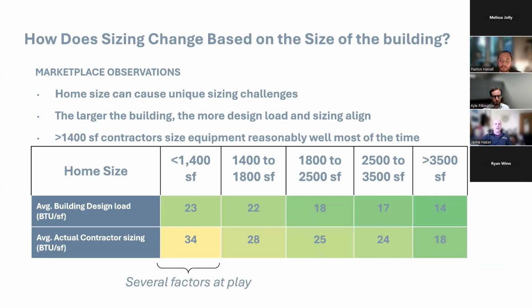As the house gets bigger, the design load of the heat pump and the sizing tend to align more. It's not hard to size a heat pump properly if they're doing the right calculations, but it is harder to do it in a smaller house. So the larger the building, the more likely it is to be sized correctly right off the bat.